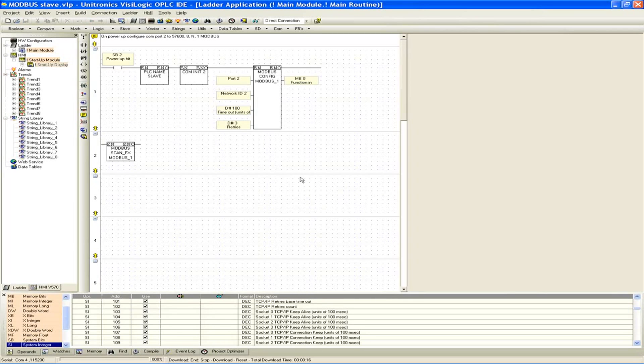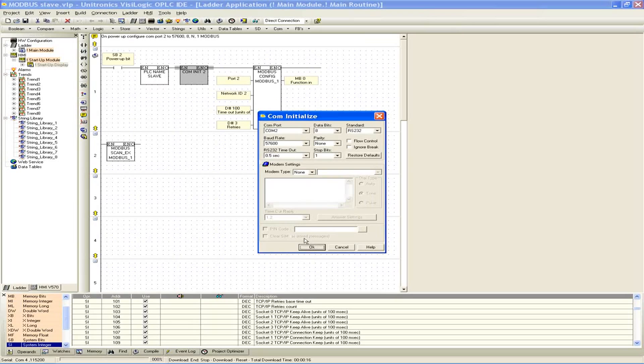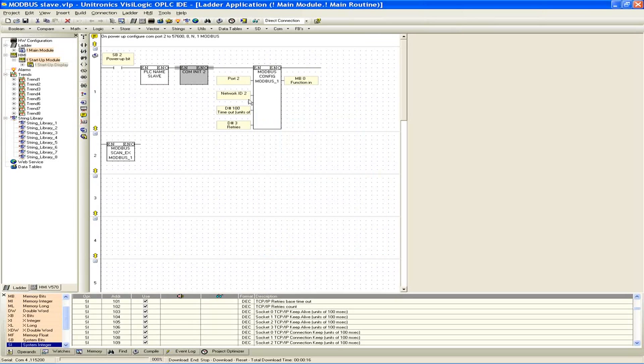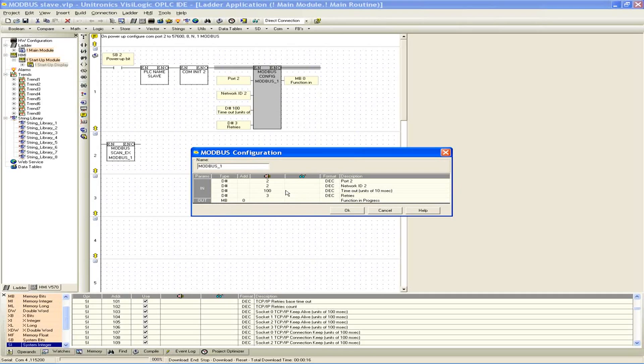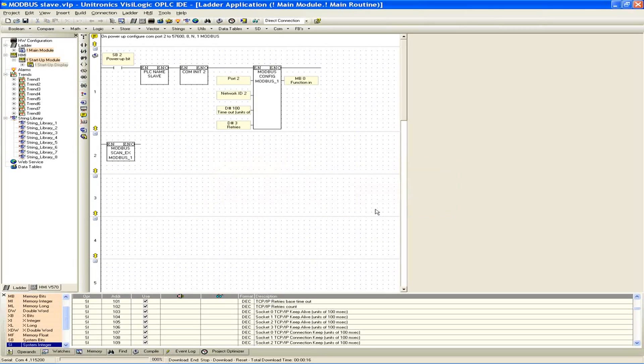So you can see there's not a whole lot going on in the slave program. Same as the master, we set up our PLC name. We set up our COM initialization block. Also our Modbus config, in this case you can see we're also using port 2, but the network ID is 2, which is why in our master application we were targeting our network ID 2, we were targeting our slave, which you can see here is defined as network ID 2. And just the standard units of time for 100 and 3, and our memory bit function in progress, which really isn't used to function in progress in the slave application, but you still define it anyway.